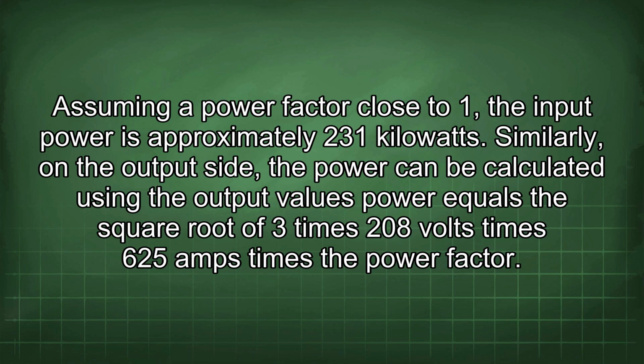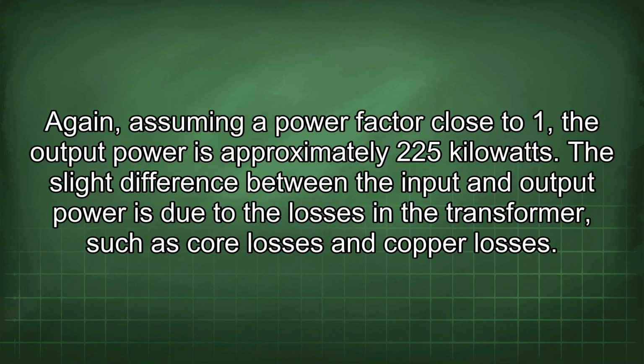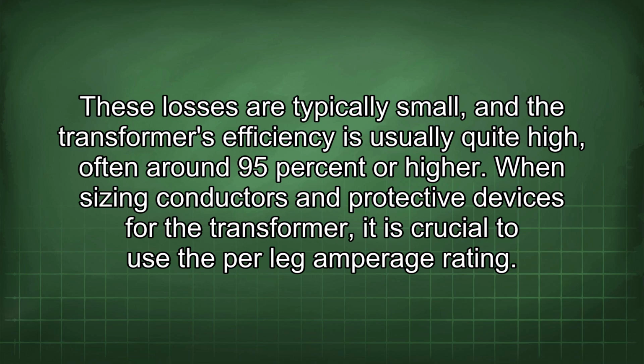Similarly, on the output side, the power can be calculated using the output values: power equals the square root of 3 times 208 volts times 625 amps times the power factor. Again, assuming a power factor close to 1, the output power is approximately 225 kilowatts. The slight difference between the input and output power is due to the losses in the transformer, such as core losses and copper losses. These losses are typically small, and the transformer's efficiency is usually quite high, often around 95% or higher.